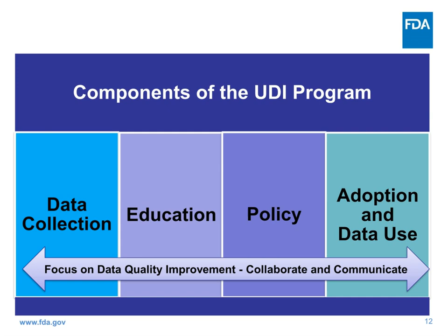So I also wanted to share some lessons learned over the last 3 years in the adoption activities specifically. Those are related to the importance of the device identifier. I broke up the UDI into the device identifier plus the production identifier. Over the course of the last 3 years, we've realized how important that device identifier is on its own and how important it is to break up the UDI into those production identifiers as well. Because the device identifier is the key to that UDI database, and as I've mentioned, it can be a link across data sources if all data sources capture that DI in a separate field.